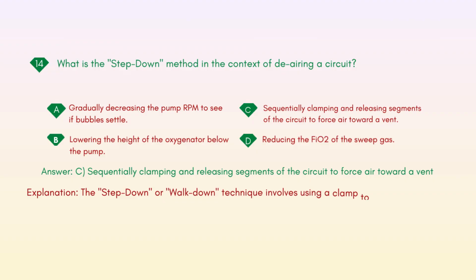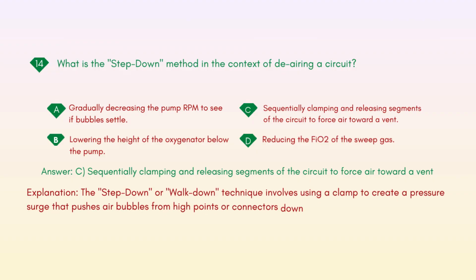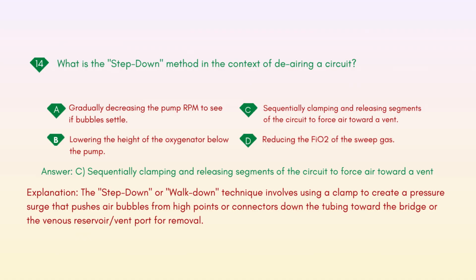Explanation: the step-down or walk-down technique involves using a clamp to create a pressure surge that pushes air bubbles from high points or connectors down the tubing toward the bridge or the venous reservoir/vent port for removal.